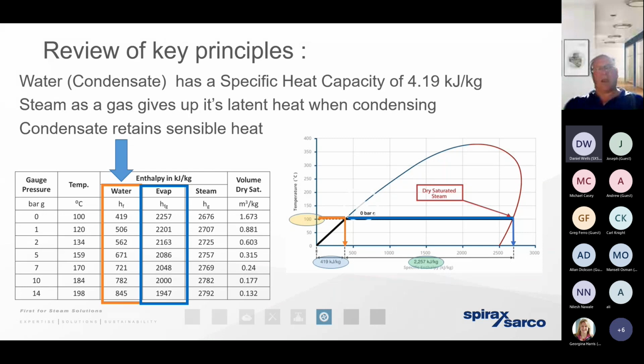Now, in reality, our client is going to be generating steam at higher pressures. We'll use the example of 10 bar gauge. At 10 bar gauge, the benefits are that the steam is going to have a higher temperature. Because of the pressure, it's going to have a smaller volume, and therefore we can distribute it in a smaller, cost-effective infrastructure. It also means we've got some good motive energy in the steam as well. We're likely to be able to distribute it hundreds or even thousands of meters to the point of use.